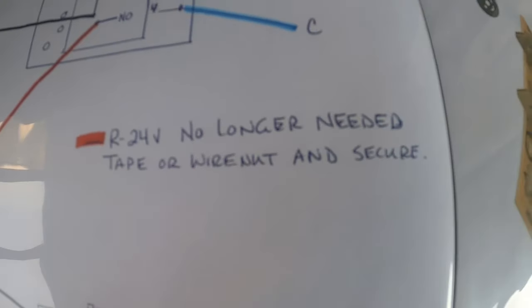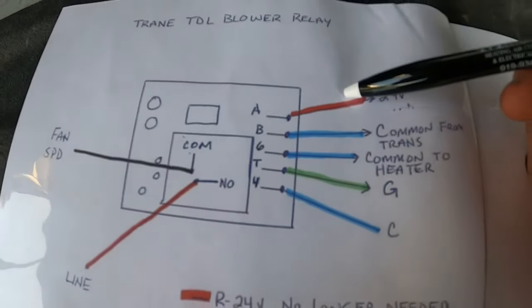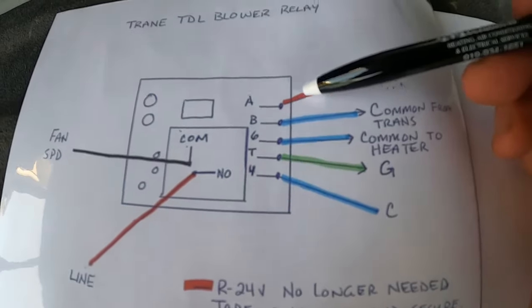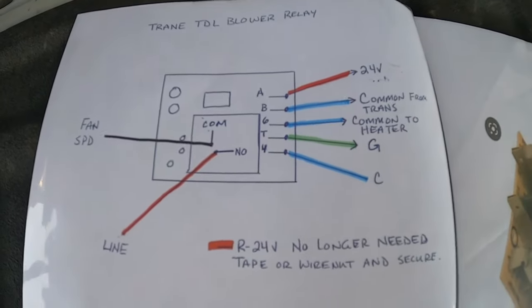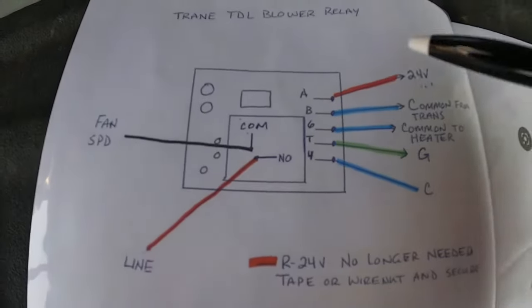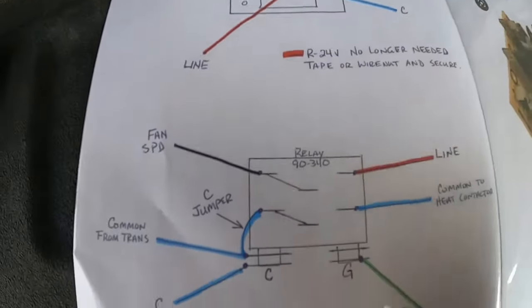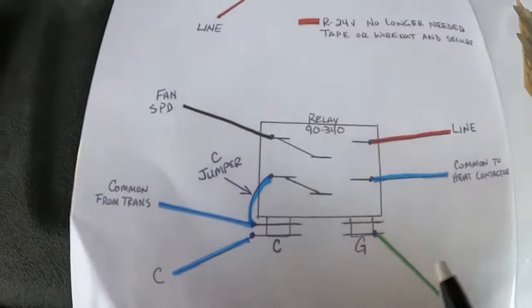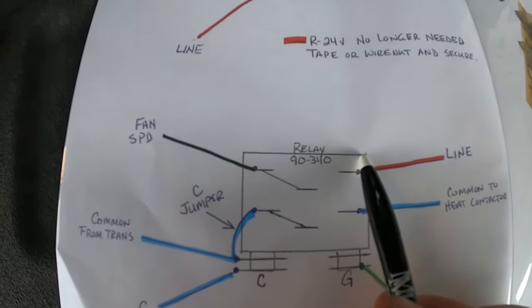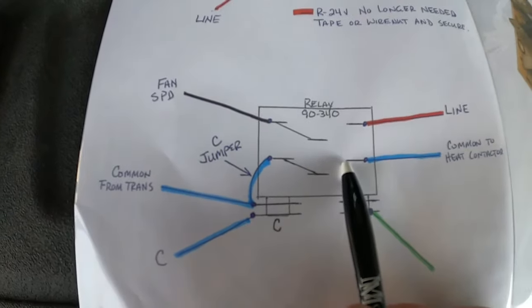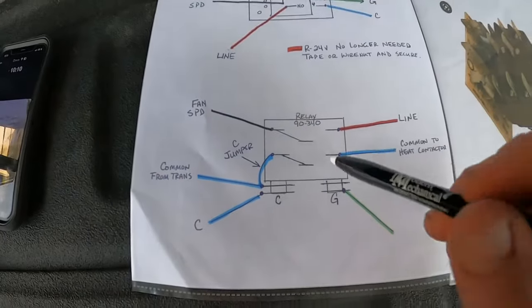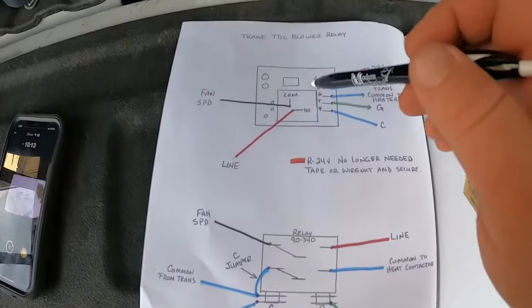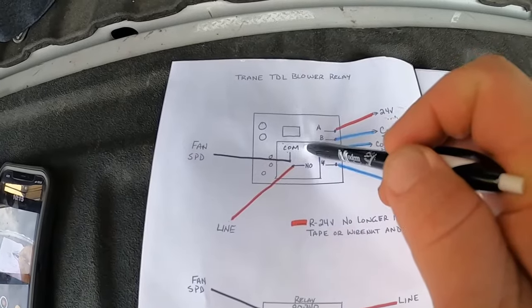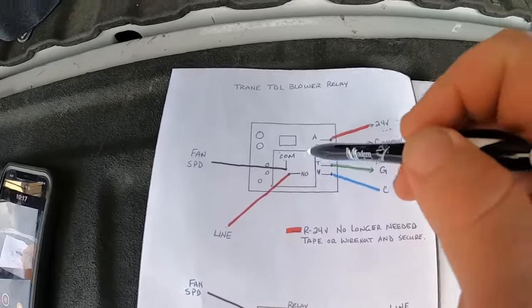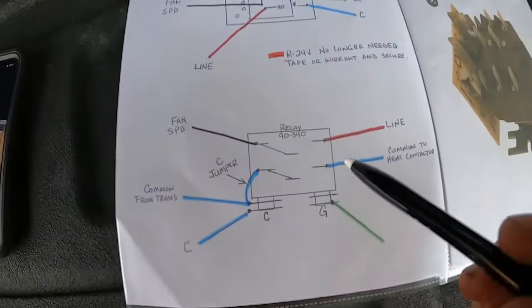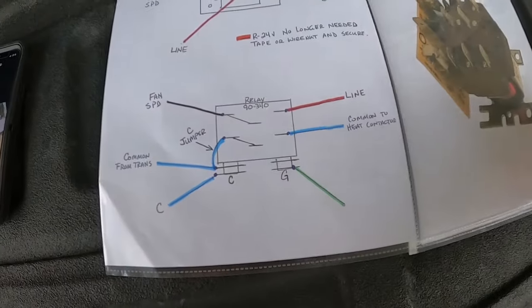And then this is what tells them the unused 24 volts: put a cap on it, wire nut. It's not used anymore, don't need it. The only purpose was to power that board. We don't have that board anymore, so we don't need that. We just need to power the blower, and we need to prove common to the contactor, and then that shows you how you can replace this relay in a pinch, this time delay control board for the blower in the Trane air handlers, with this 9340 relay.